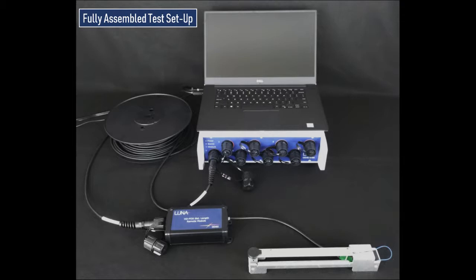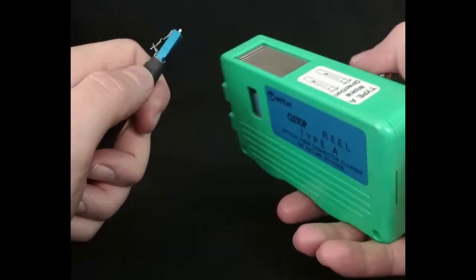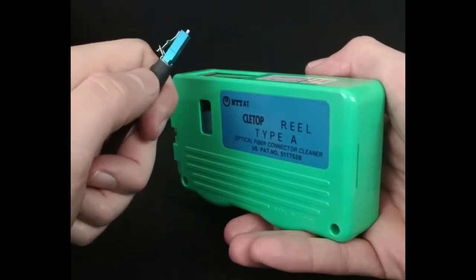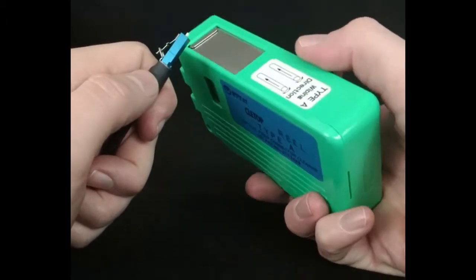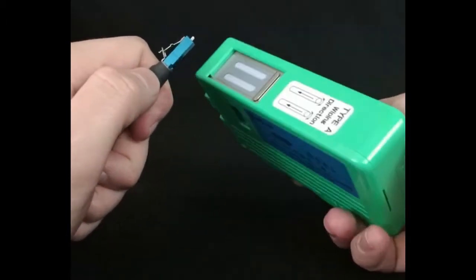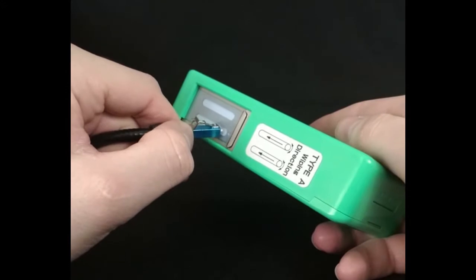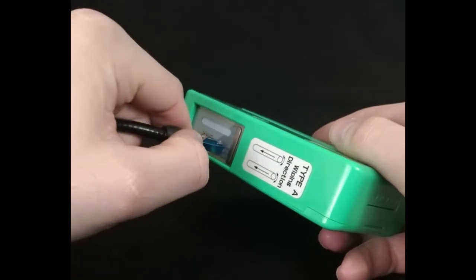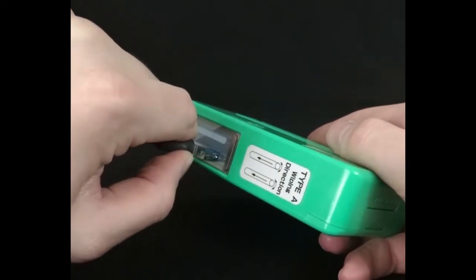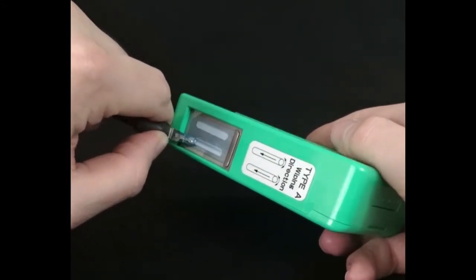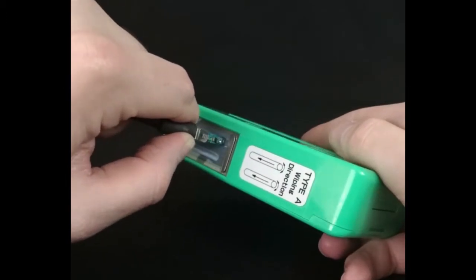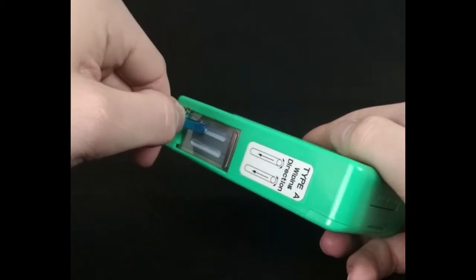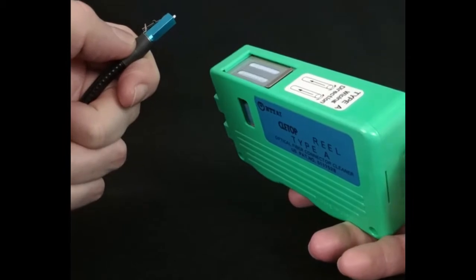It is important to note that during assembly, all connectors should be cleaned to remove any dust or particulates that could lower the quality of the optical signal. This can be done quickly and easily by using a Cletop device. Simply pull back the lever to provide a strip of cleaning material and press the connector face to the surface. Make a quarter turn and drag the connector across the strip. This should be done for all connectors on standoff cables, remote modules, and sensors.